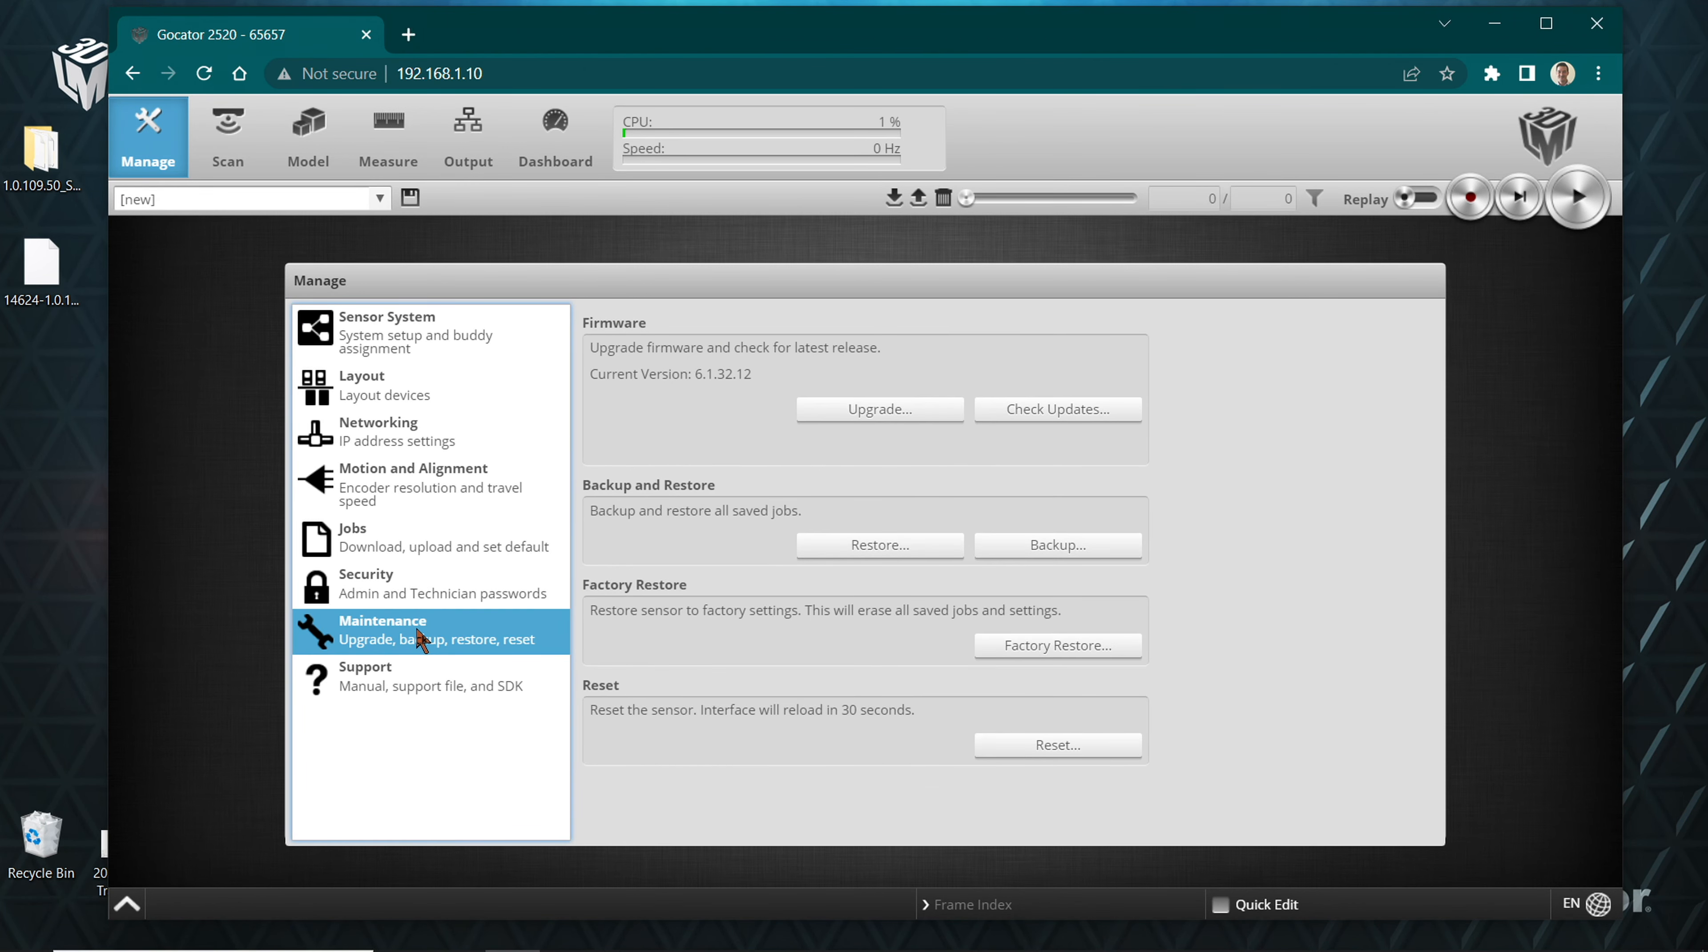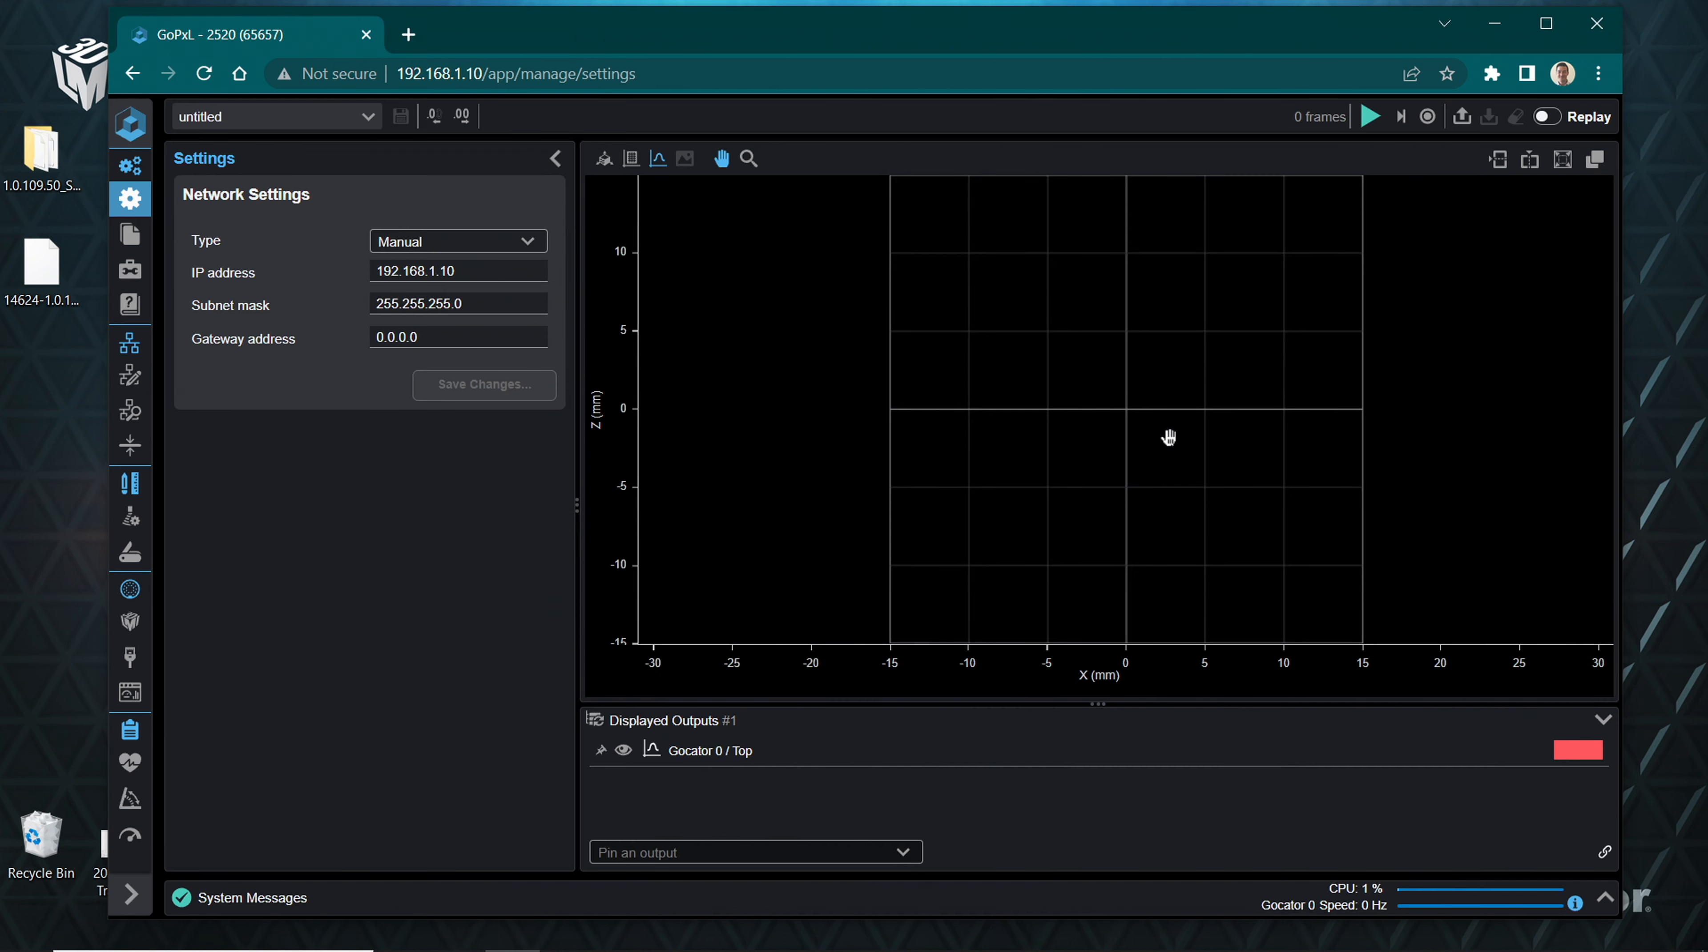Navigate to the Manage page, click on the Maintenance panel, then click Upgrade. Select the DAT file specific to your sensor model that you have previously downloaded. Wait for the firmware to upgrade and interface to reload. GoPxL will refresh within the same browser window.